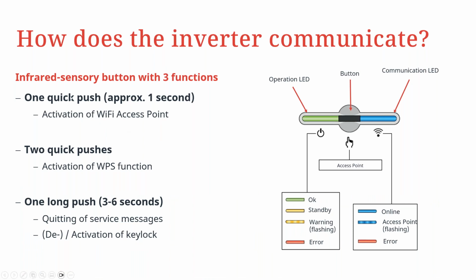There are various ways that we can communicate with the inverter using the touch button. One quick push for approximately a second, as seen in the previous slide, automatically activates the Wi-Fi access point. Two quick pushes activates the WPS function. WPS here simply means Wi-Fi Protected Setup. With this, it basically bypasses the use of passwords. Once you activate the WPS function, you can connect the inverter to the internet without the use of passwords. One long push for about 3 to 6 seconds deactivates service messages, and this also either activates or deactivates the key lock.